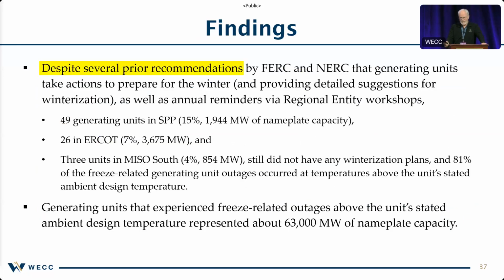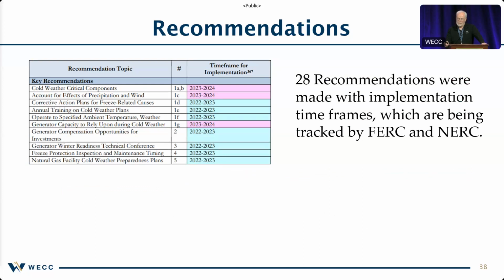What did they have for findings? Despite several prior recommendations, 49 generation units in SPP, 26 in ERCOT, 3 in MISO South, still did not have any winterization plans. And 81% of the freeze-related generating outages occurred at temperatures above the unit's stated ambient design temperature. So we're still tripping above the design temperature. We're still having prior recommendations not being followed. And in this particular one, 28 recommendations were made.